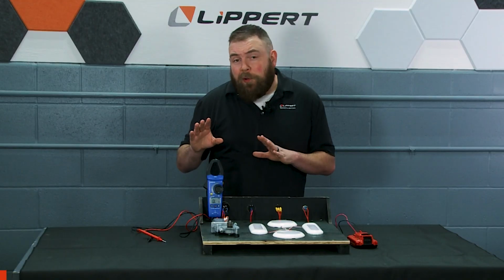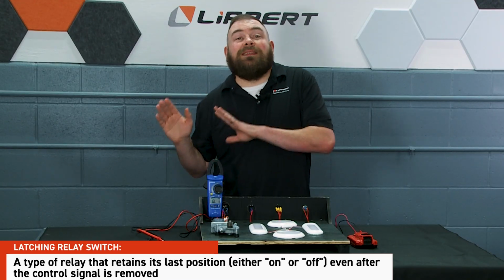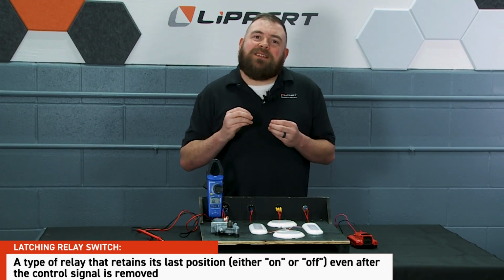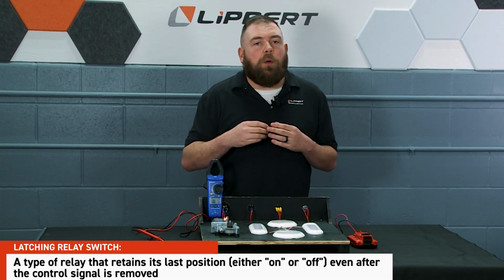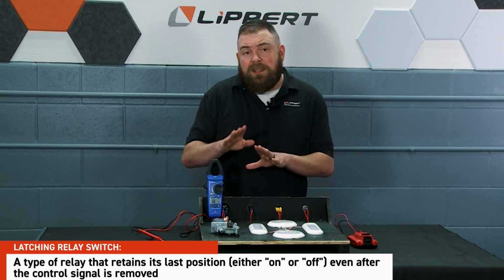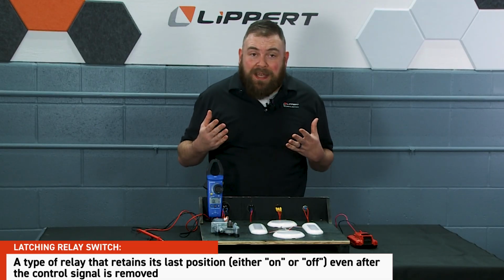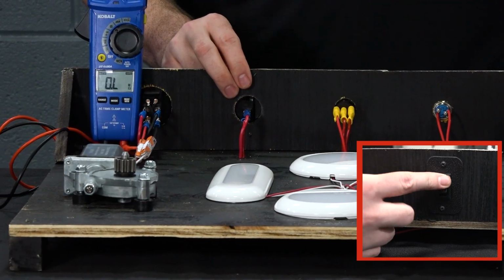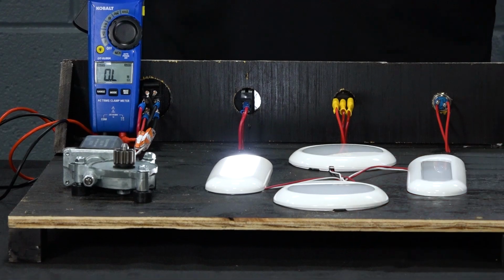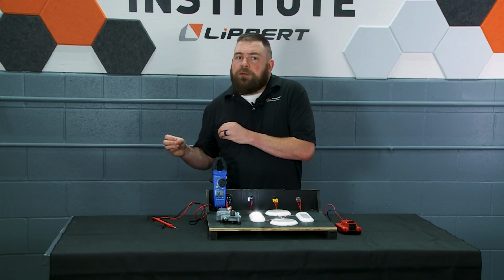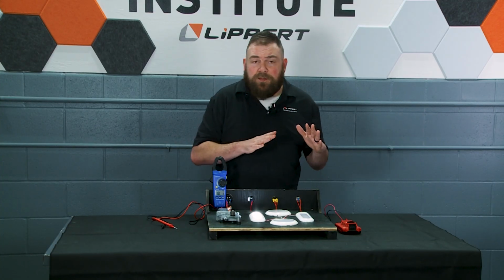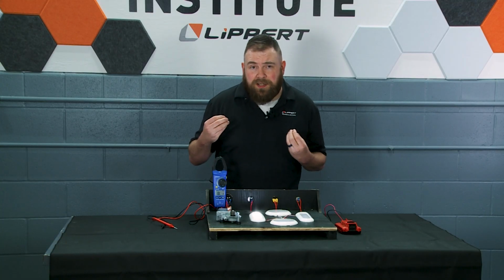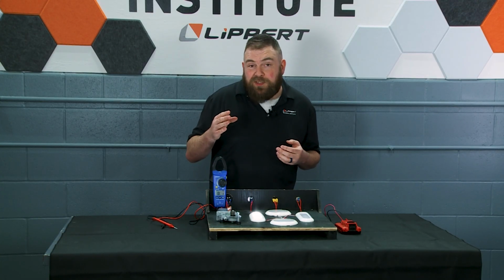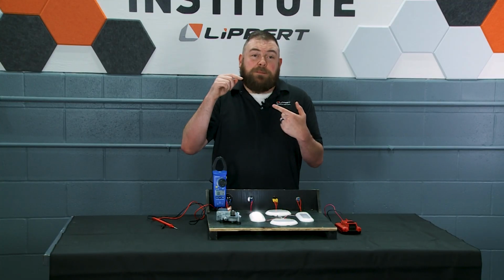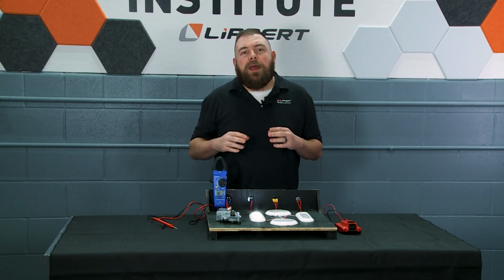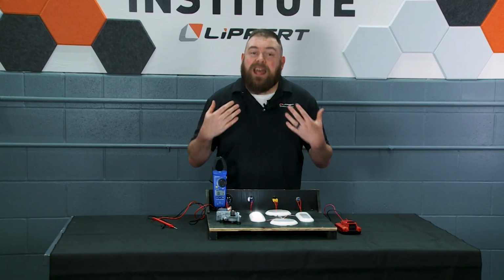Well, simply put, a latching relay is going to latch into place when it is either in the on position or the off position. We can see here I have a light connected to my latching relay, and really if I turn it on, we can see that it has then created continuity. We don't troubleshoot it in a manner that's any different than the others. We are going to use the continuity setting, and just like we did for the momentary switch, we are just going to touch both spades, and if we have continuity, it means the switch is healthy.